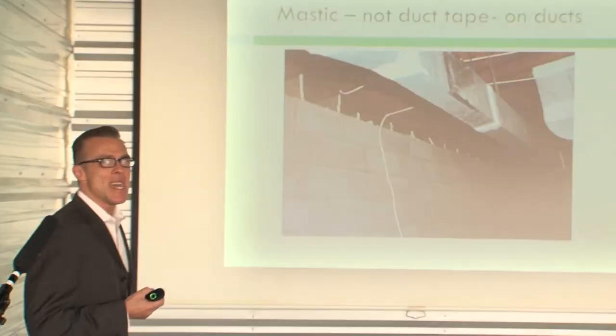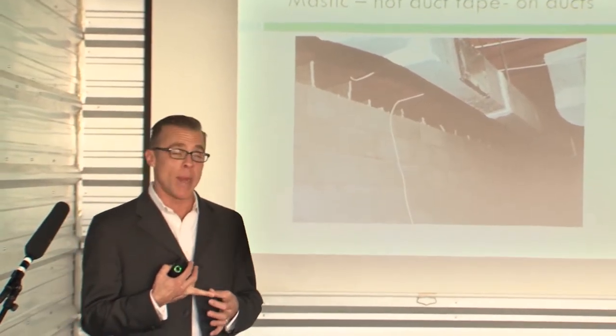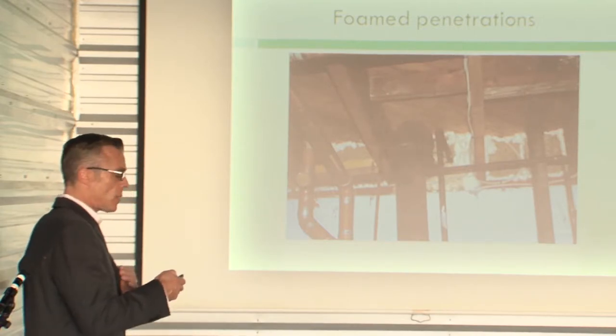There are a bunch of different ways of sealing up ductwork. You see foil tape here, and this gray material is called mastic — a semi-elastic nail polish-like substance that gets painted on and seals up. You've all heard the MacGyver analogies — duct tape is great for lots of things, but not ductwork. This is not the prettiest picture, but it was a difficult scenario: gas lines, refrigerant lines, drain lines, soil waste lines — everybody poked a hole in the rim joist around here. It's certainly not beautiful, but it is not leaking air anymore. It's all part of fighting the same battle — also solving pipe freeze issues.